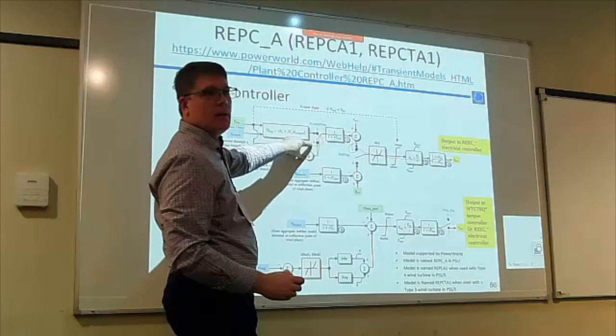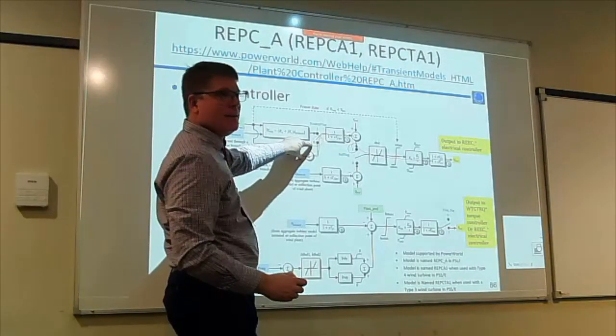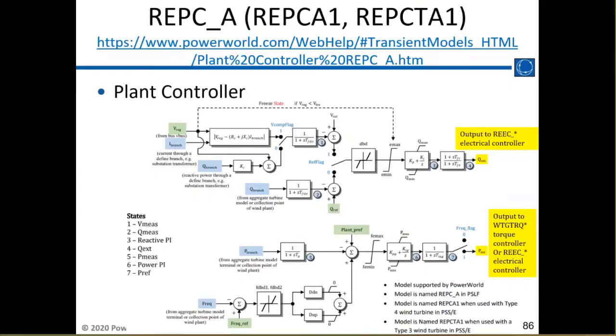It's an error on the block diagram, the pluses and minuses aren't there. I'm pretty sure it should be voltage minus Q times Kc, so that as the reactive power goes up, the voltage set point goes down. So you're going to be regulating against a curve like this, where as the voltage goes up, I want the Q to go down.